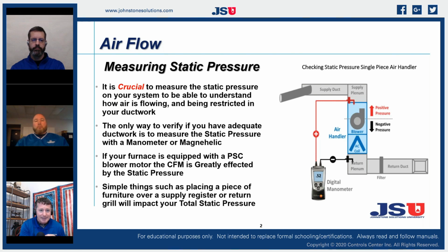I actually had one last summer that I went and did a tech support site visit on. The readings that I was getting from the technician didn't jive. The pressure readings that he had on the return and on the supply were in the 0.6 to 0.7 range. But yet he was having blower fault codes. That ECM blower motor was tripping out on an internal overload.